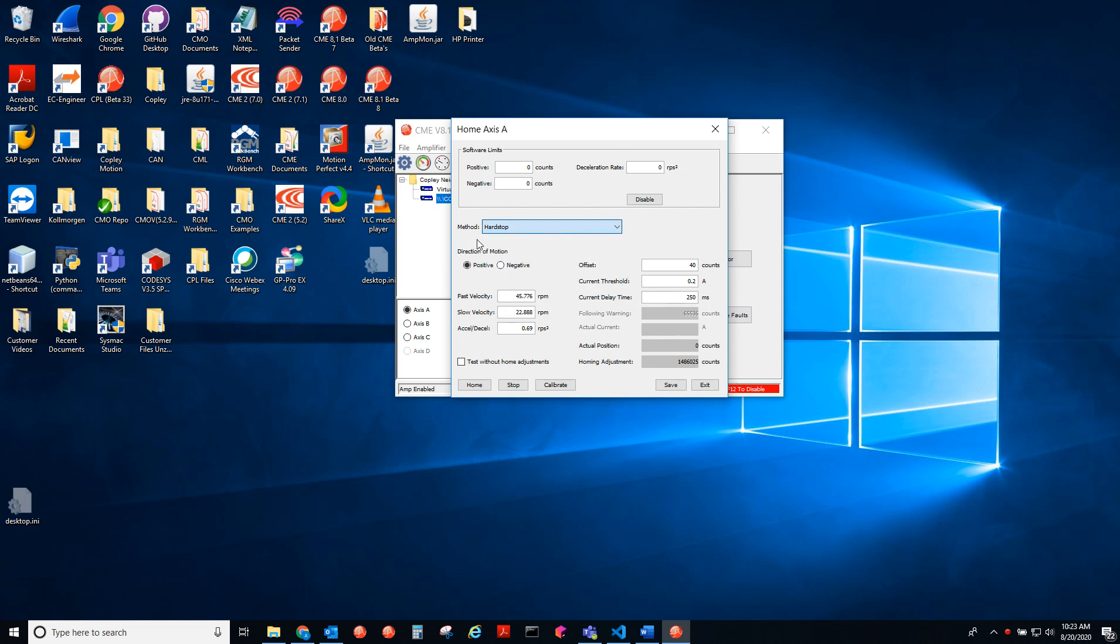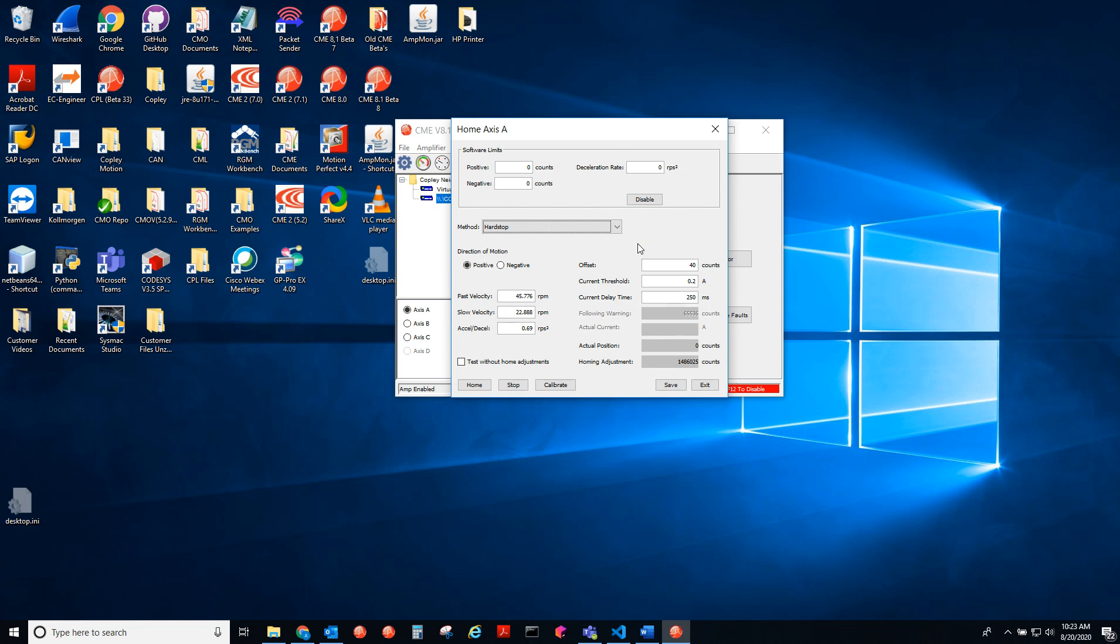Here I'll be testing a hard stop in the positive direction. This offset of 40 counts isn't applied until after the hard stop has been reached. So you jog in the positive direction, hit the hard stop, which means that the current will exceed 0.2 amps. That's how the drive knows that it hit the hard stop. Then they'll go in the negative direction 40 counts and set that equal to the new zero position.